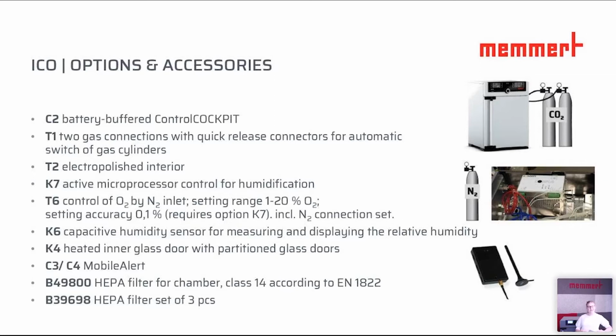Also interesting is our option T6. With that, you can control the O2 concentration inside the chamber by an N2 inlet. And you will be provided, as discussed before, with an O2 setting range of 1 to 20%. But Memmert can also provide a mobile alert with their option C3 or C4, which basically sends you a message either per SMS or per email in case of error with the appliance. If you're interested in a HEPA filter, you have the possibility of purchasing that.